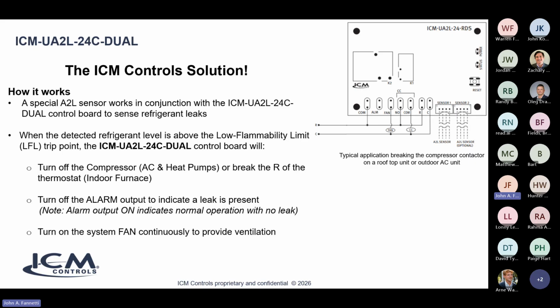Note the alarm output is opposite of what you might think. Normally you would think that you'd see a light go on, but in this case you want to have a light on all the time so that in dark locations or when a person's checking the system, they can actually look inside, hey, my light's on, I'm good. If they don't see the light, then they know they got a problem. So it's a little way of giving you an easier way to check whether your system is functional or not. And then turn on the system fan, to just create circulation and aerate the area from that low flammable refrigerant.